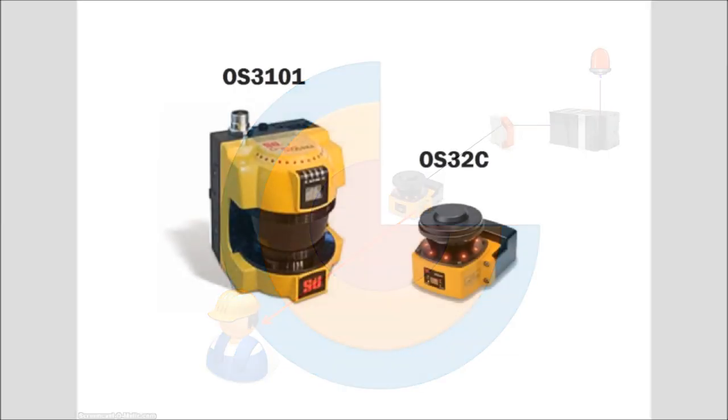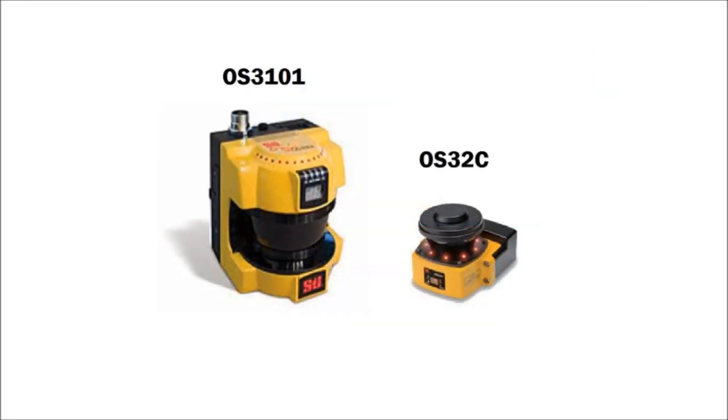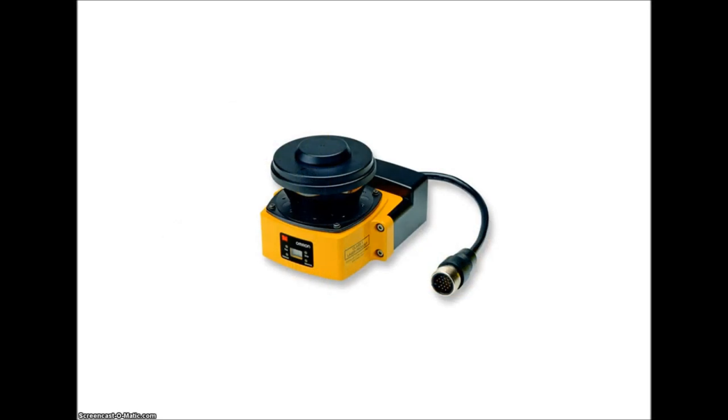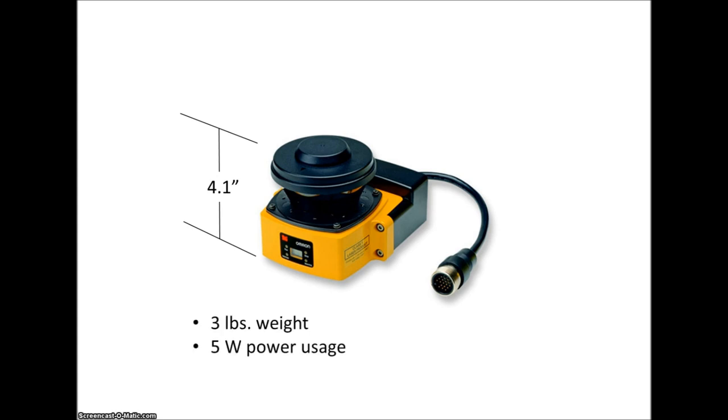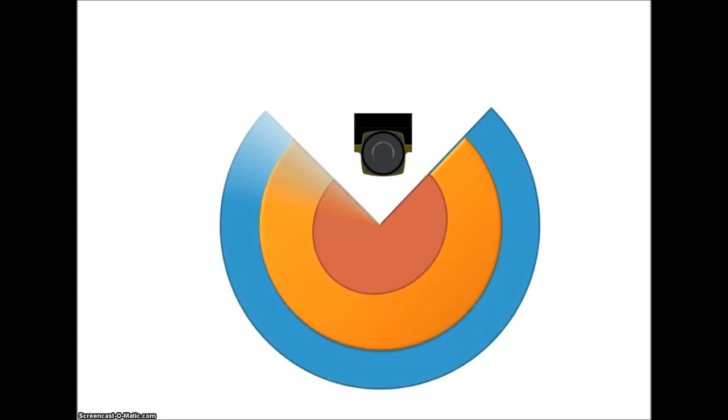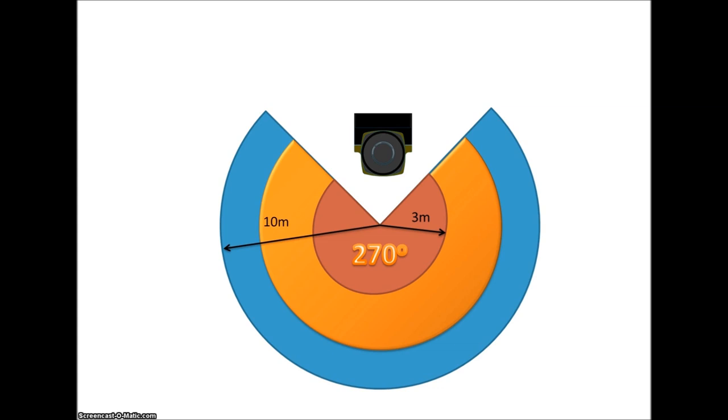The OS-32C is the smaller of two series of safety area scanners that Omron STI offers and is an industry leader in its compact size with a height of only 4.1 inches. It is also lightweight at only 3 pounds and consumes 5 watts of power. The scan area allows 270 degrees with a safety radius of 3 meters and warning zones up to 10 meters.